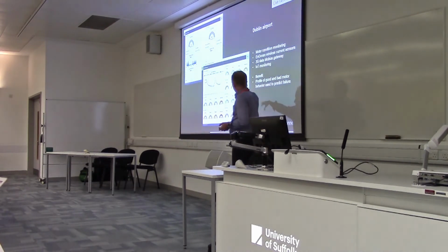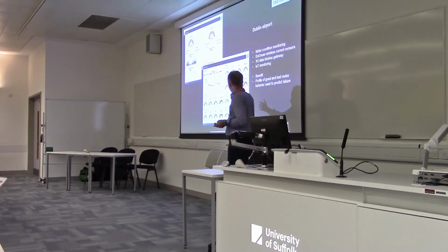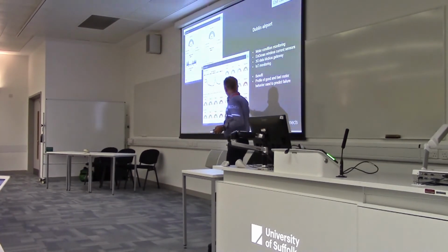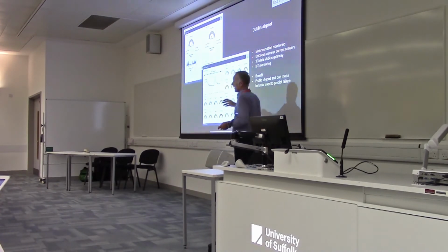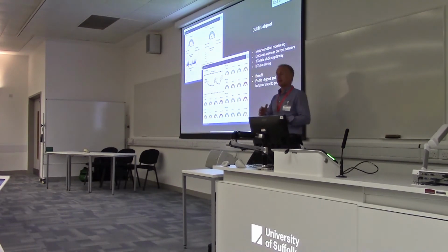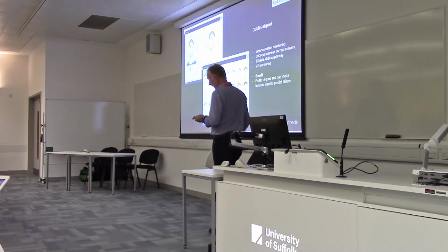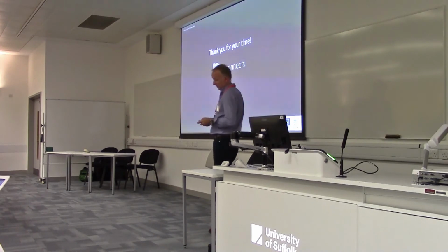And this dashboarding thing is, again, I say we don't do dashboarding as part of the system. This is something Node-RED offers, it's an IBM tool. So it gives them the ability to look at a phone, and the engineering manager looks at his phone, and within a day of firing the system up, they realised that they had a phase imbalance because they were monitoring current, across the three phases, which was one of the things that was causing the problems. That was a byproduct of what they did.